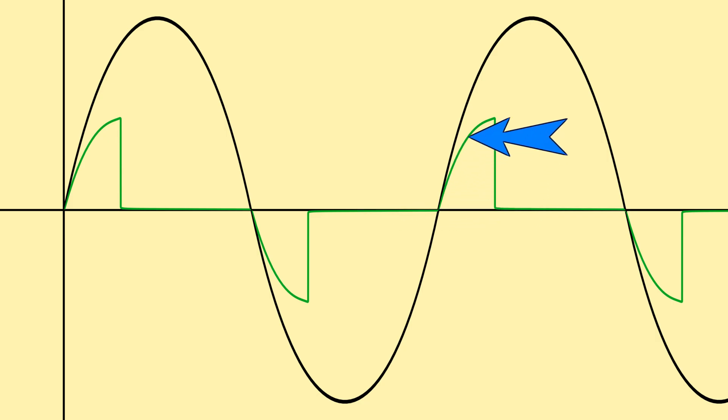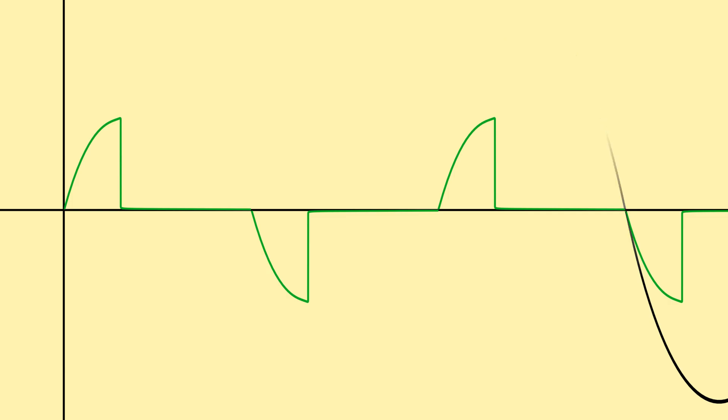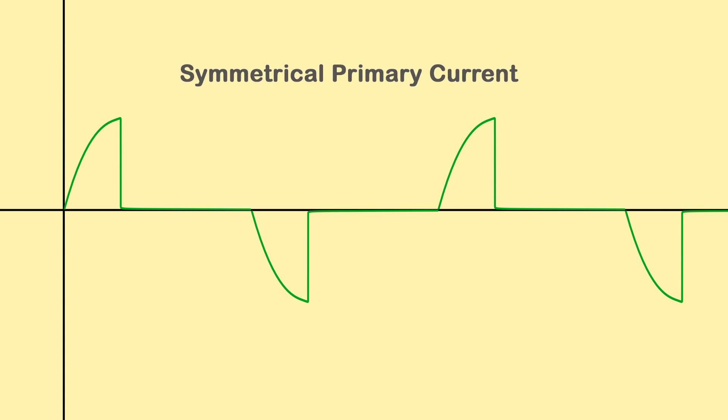This pattern will continue until the primary current drops below the saturation threshold. If we observe the secondary current alone, it appears as a distorted waveform — obviously not sinusoidal. This distortion may introduce harmonics into the secondary current. We have discussed the saturation phenomenon of a current transformer with symmetrical primary current. However, there is another kind of saturation that occurs in the core due to asymmetric current in the primary circuit. Asymmetric high current in the primary circuit is mainly caused by a system fault. That topic will be discussed in another video.